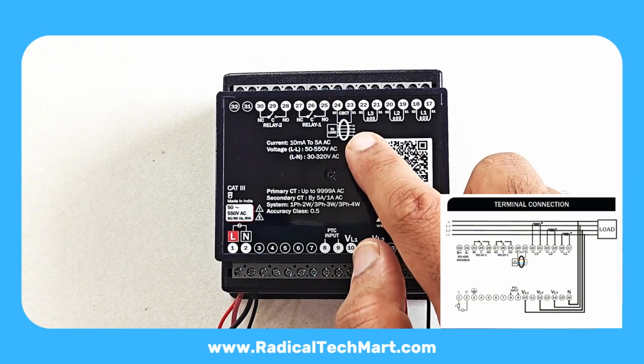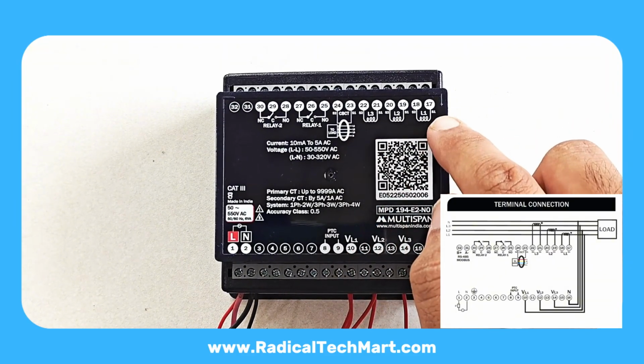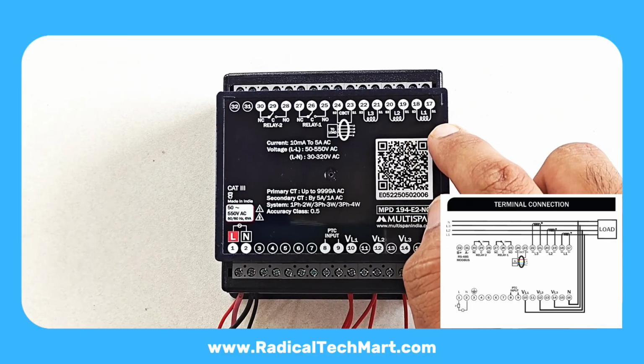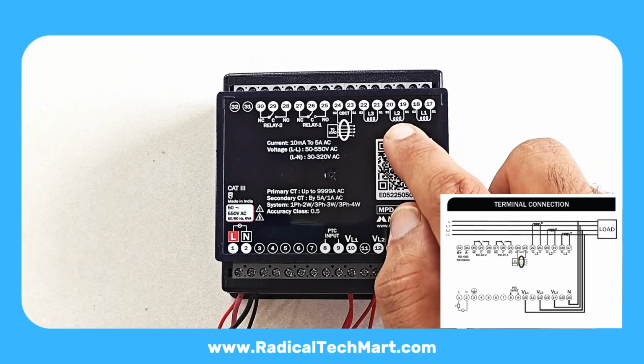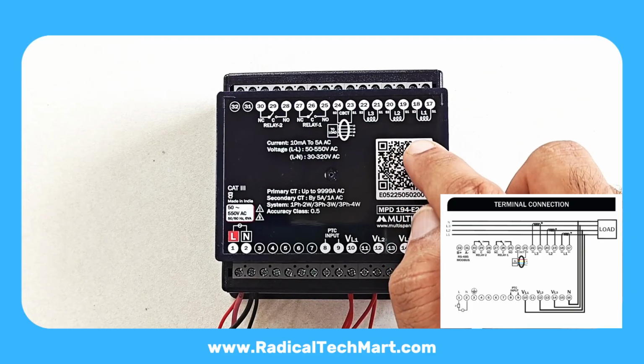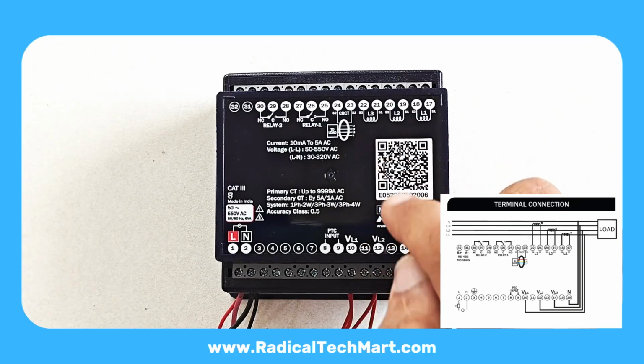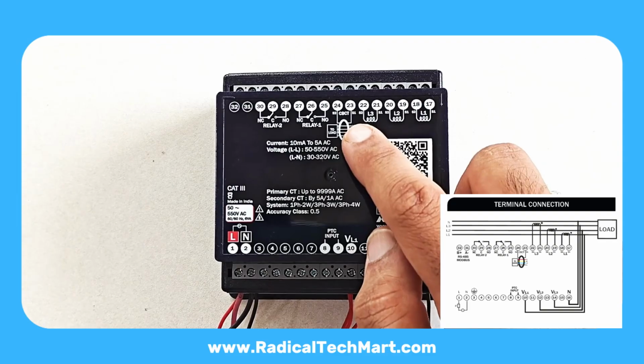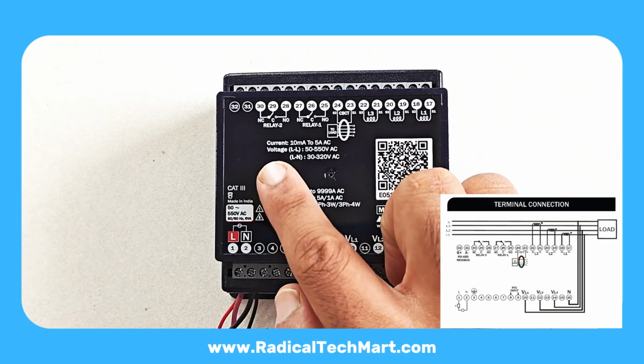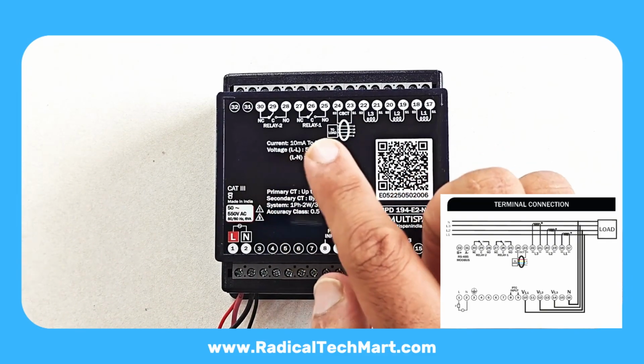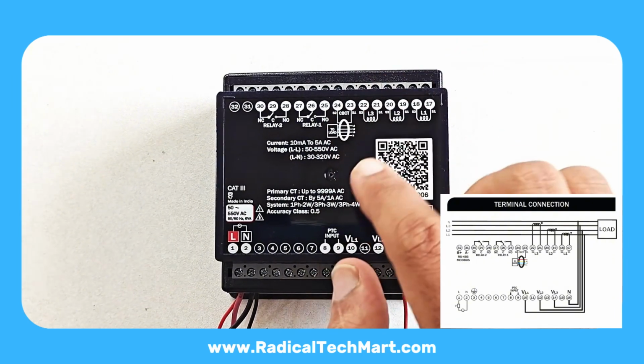Terminal 17 to 22, phase CT inputs. 17 and 18, CT for R phase, S1, S2. 19 and 20, CT for Y phase. 21 and 22, CT for B phase. Current input range, from 10 mA up to 5A, CT secondary.